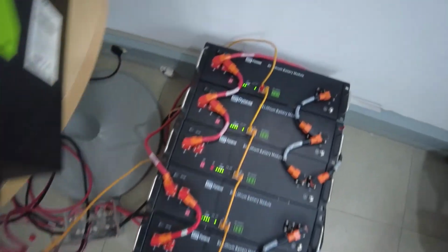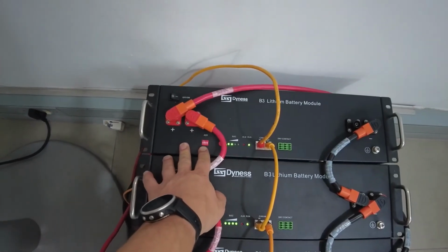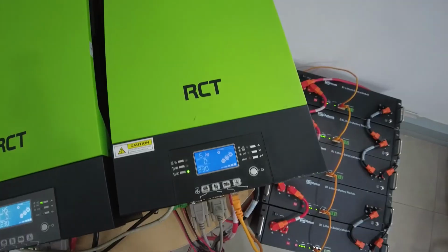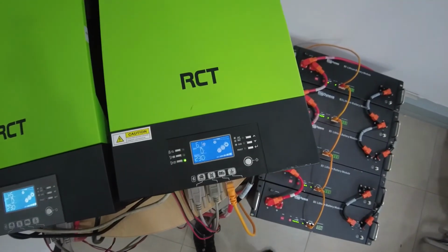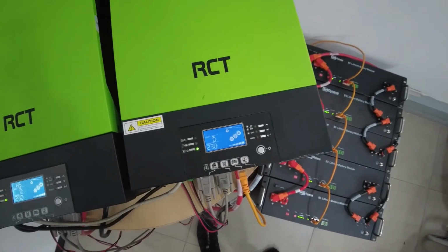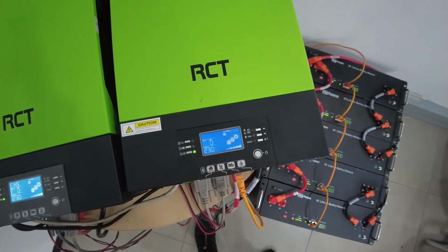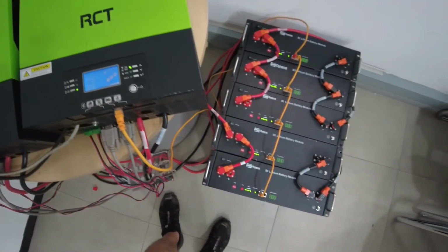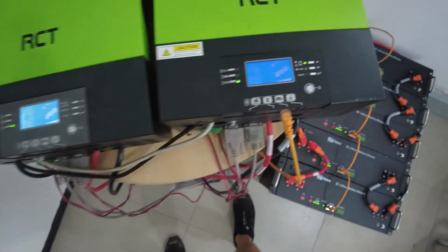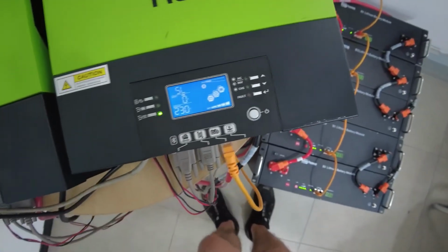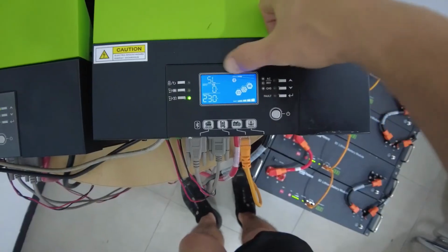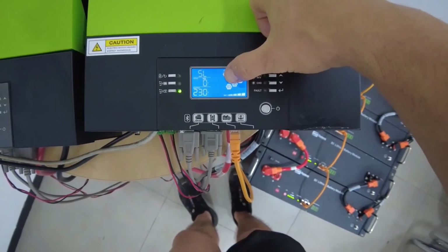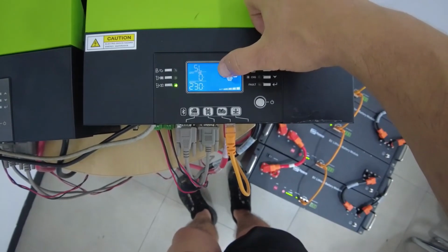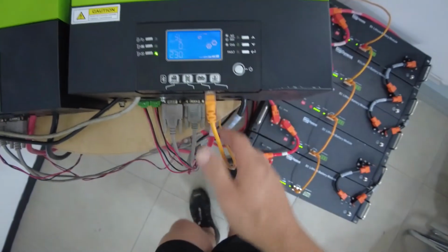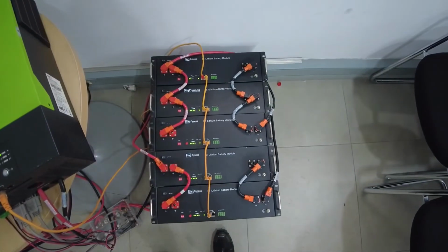Connecting the BMS cable. Now, as previously mentioned, this is the cable running to your master battery that we've set to the DIP 0100. Just give it some time. Normally it takes about a minute to establish BMS communication if your cable pinout is correct. There we go. So currently you can see the 61 has been cleared and the battery icon is flashing. The flashing battery icon means the battery BMS communication is established and it is communicating with the set of batteries.